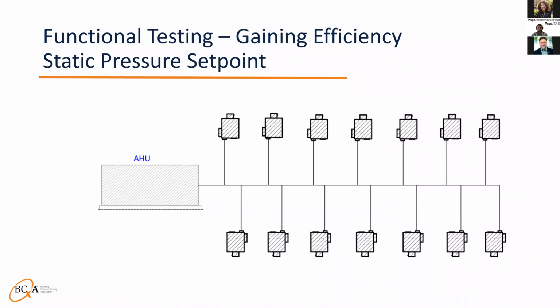Now, if there is diversity, there are a few ways to take that into account, but I'm going to tell you the way I like to do it. For those of you that don't know, diversity is when the terminal unit max cooling CFM is higher than the design CFM of the AHU. The engineer anticipates that the building will never see full design flow, usually because people will not fully occupy the AHU's associated spaces. So the process for determining static pressure set point on a unit with diversity starts out the same as if it doesn't have diversity.